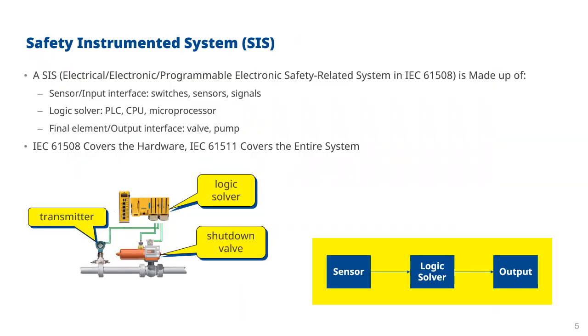So a safety instrumented system is an electrical or electronic or programmable electronic safety related system, and it's made up of the sensor or the input. That can be switches or sensors or signals or other sorts of detectors. We have a logic solver, which is the PLC with its CPU and microprocessor, and then there will be a final element or an output, which could be a valve or a pump. Now there are standards that cover these. In general, IEC 61508, that's the standard that covers the hardware, but there's another standard called IEC 61511 that covers the entire system.